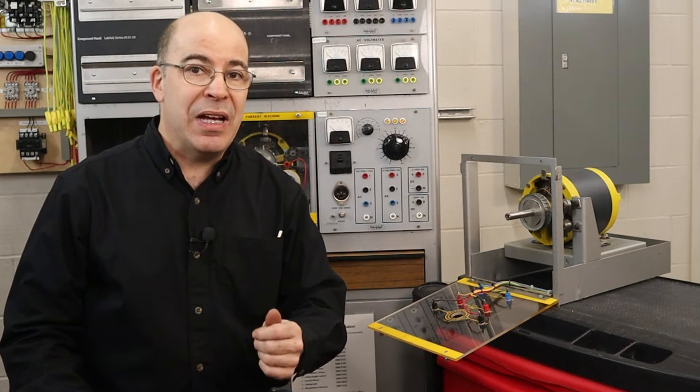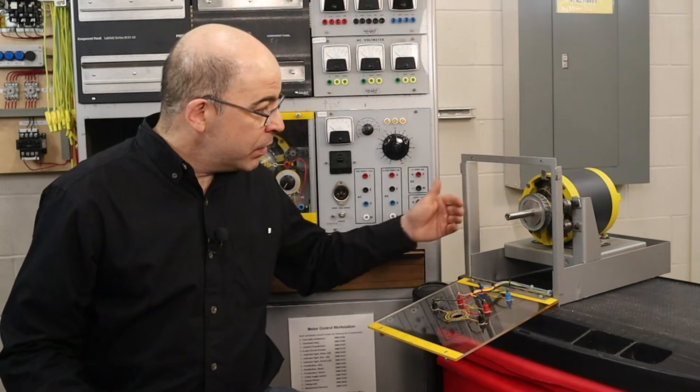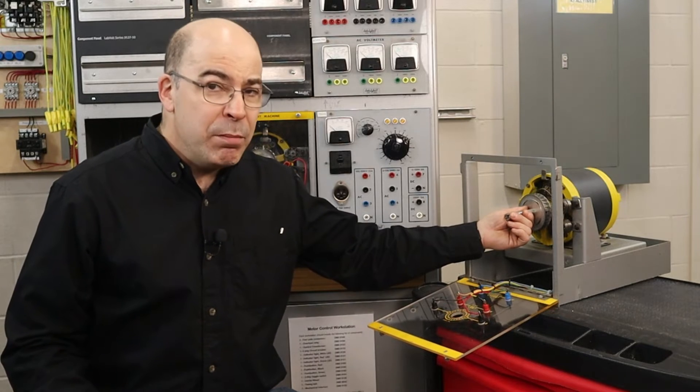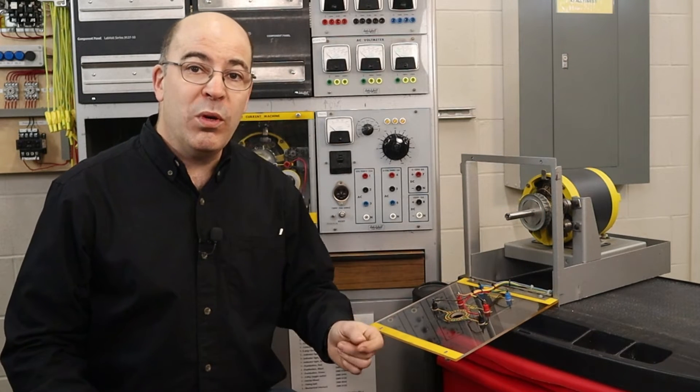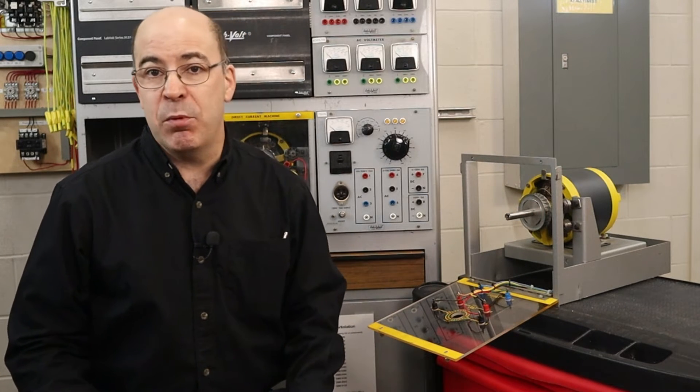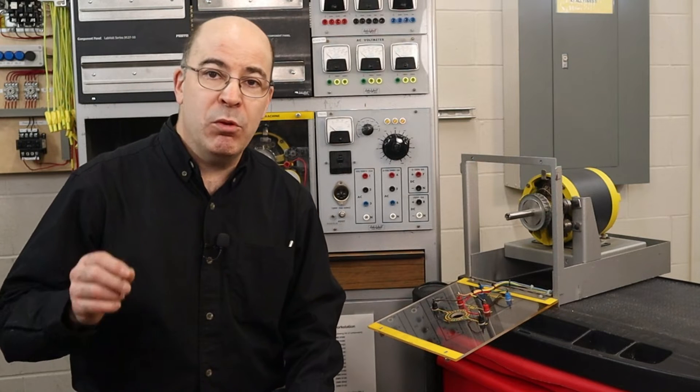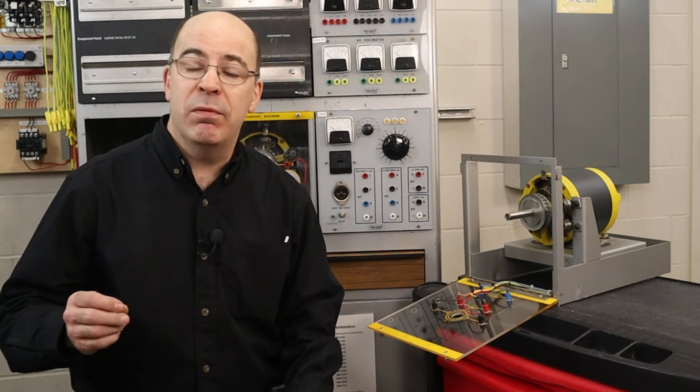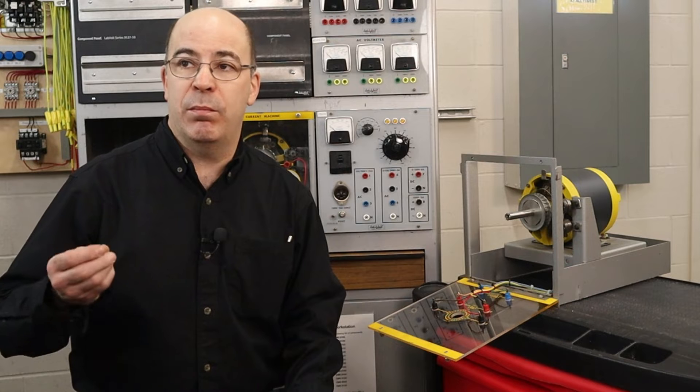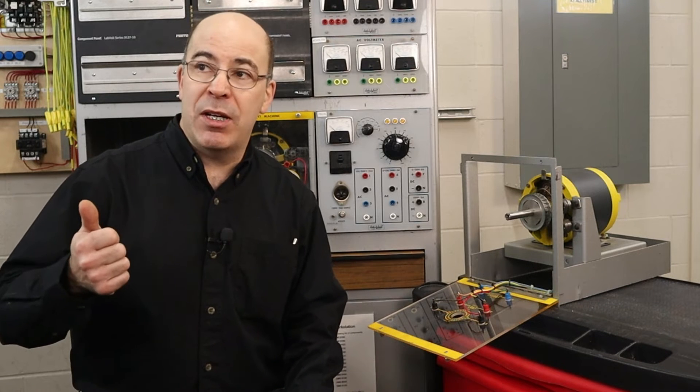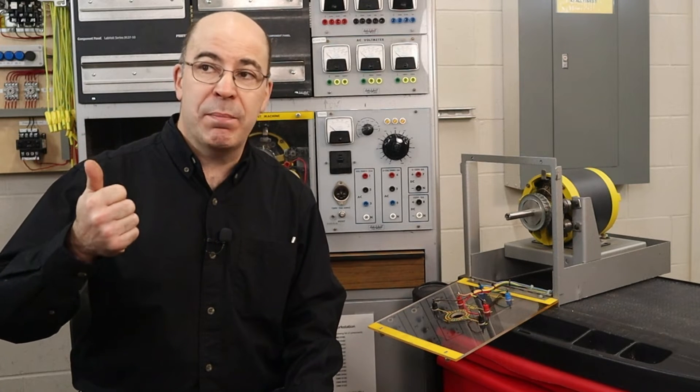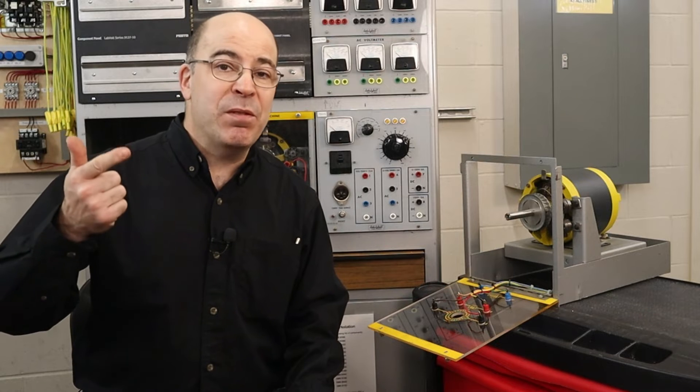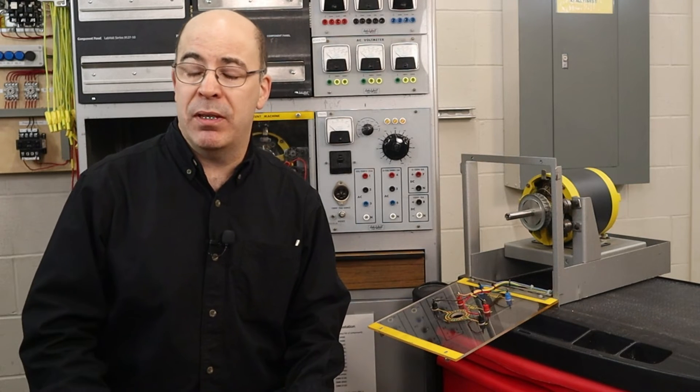By not setting the brushes, I'm not going to be able to develop the kind of power that the motor is capable of delivering or the rated speed that it's supposed to operate at. So that's one of the more important takeaways of why we want to set the brushes. I want to make sure the motor can produce the horsepower it's supposed to at the speed it is supposed to be able to deliver it at.